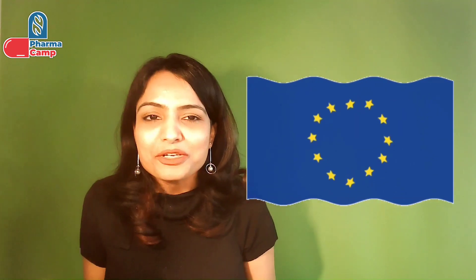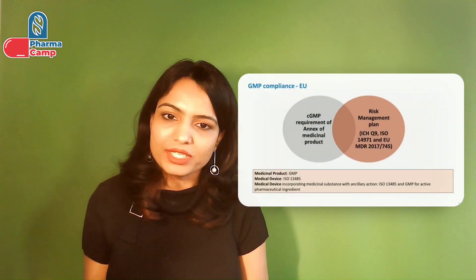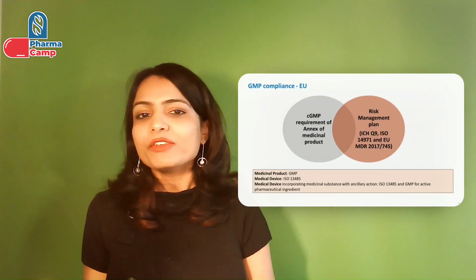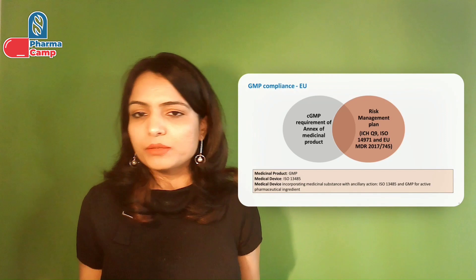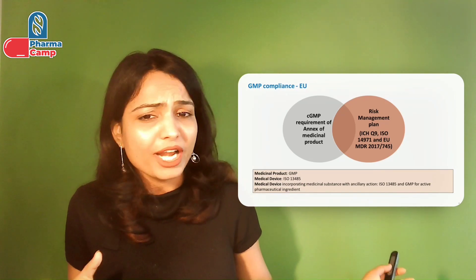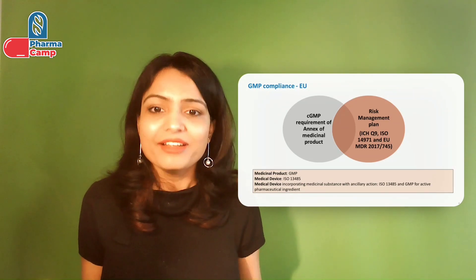Now let's move to the EU. As discussed, in the EU there is no separate regulation for combination products, so your product will either be regulated as a medicinal product or a medical device depending on the primary mode of action. If the primary mode of action is due to the drug, you need to fulfill the general drug GMP requirements along with risk management following the principles of ICH Q9, ISO 14971, and EU MDR. This was the key difference in GMP requirements for combination products in the US and EU.